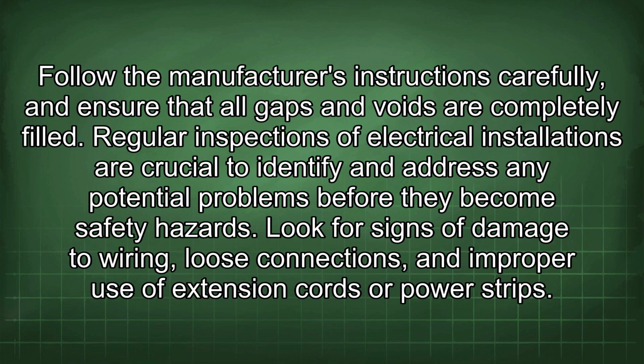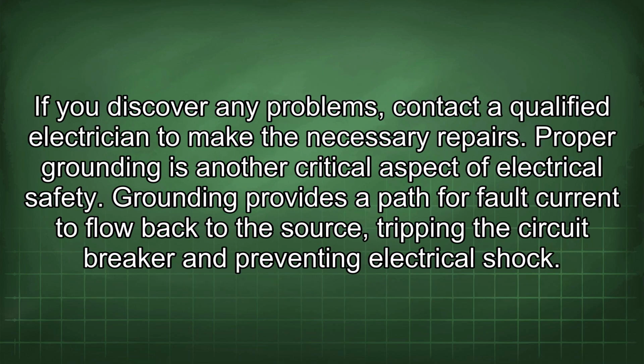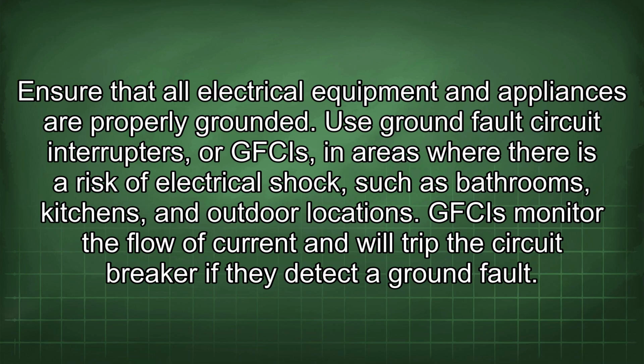Regular inspections of electrical installations are crucial to identify and address any potential problems before they become safety hazards. Look for signs of damage to wiring, loose connections, and improper use of extension cords or power strips. If you discover any problems, contact a qualified electrician to make the necessary repairs. Proper grounding is another critical aspect of electrical safety. Grounding provides a path for fault current to flow back to the source, tripping the circuit breaker and preventing electrical shock. Ensure that all electrical equipment and appliances are properly grounded.